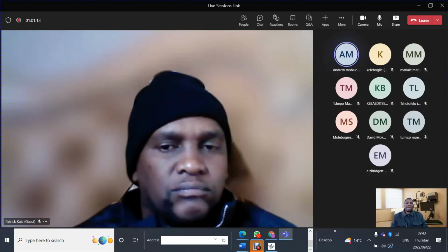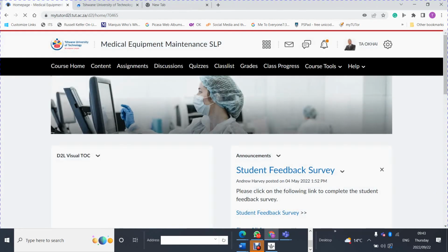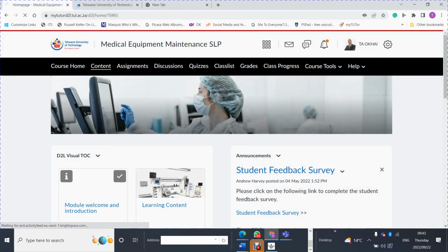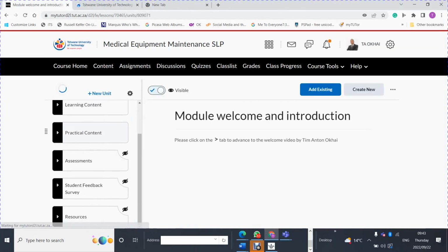Yes, I have a question. Sorry, it's Andrew, right? Yes. During the session, I saw an article which says patients must never be connected to an earth point during diathermy, as it risks a shock or a burn.